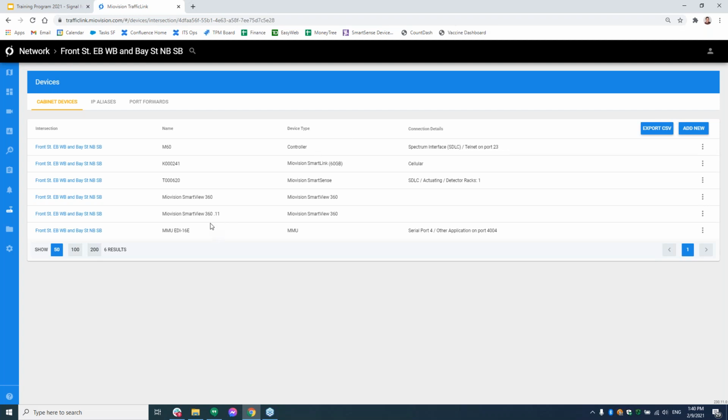The last one here that I've been using a lot lately, especially on understanding flash alerts or intersection operational alerts that tend to occur over time, and everybody being remote now in their home offices or through the pandemic, I've been noticing a big uptick on customers taking advantage of the conflict monitor access to understand a problem. So there's two different views on here, and depending on your conflict monitor, you could either connect it over serial or you can connect it over Ethernet. So you have both options. In this case, we're actually connected over a serial because it's an older monitor, I guess, but it can certainly be set up over Ethernet if we wanted to.